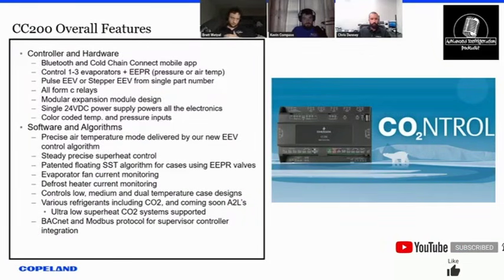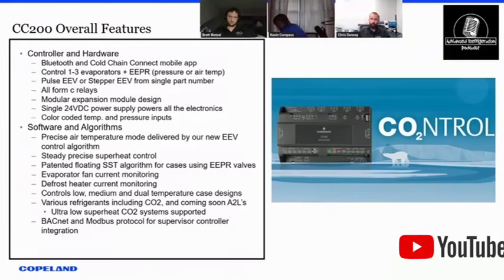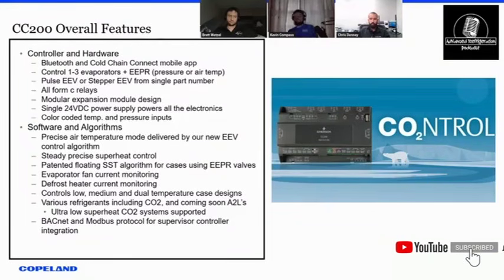With some new software features, we totally revamped and reinvented our EEV control algorithm, specifically testing it for different compression types in our labs, and specifically doing a lot of testing around CO2, because CO2 is a bit more volatile on the pressure fluctuations. Up to this point, it's basically EEV control does air temp, then you have to watch the superheat as well. All new EEV control algorithm. It's performed very well in the lab, very well in pilot stores as well.